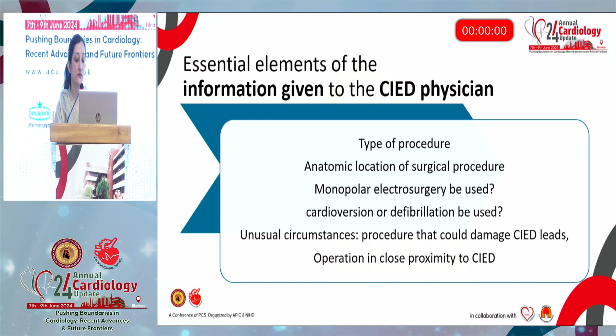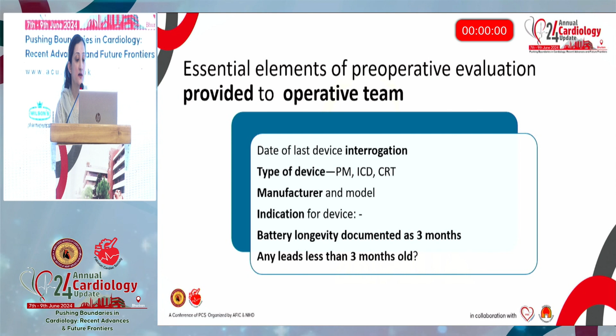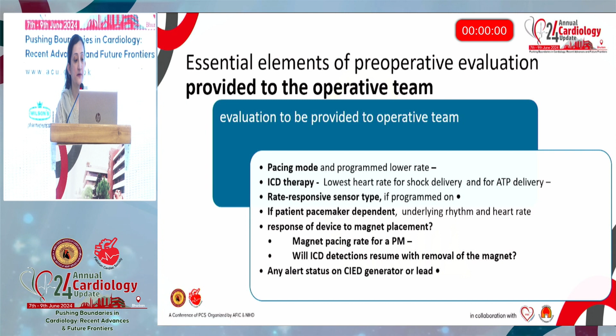The information that needs to be provided to the operative team includes the date of interrogation, type, manufacturer, and model of the device. Battery longevity is very important and is documented as 3 months because that represents the end of the elective replacement index. Also any leads that are less than 3 months old, because there is a high chance of lead displacement. Other information also includes pacing mode, whether ICD treatment is turned off, whether rate response sensors are turned off, and what will be the response of the patient to magnet application.